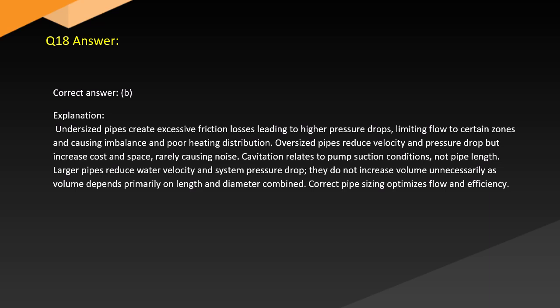Answer. Correct answer, B. Explanation. Undersized pipes create excessive friction losses leading to higher pressure drops, limiting flow to certain zones and causing imbalance and poor heating distribution. Oversized pipes reduce velocity and pressure drop but increase cost and space, rarely causing noise. Cavitation relates to pump suction conditions, not pipe length. Larger pipes reduce water velocity and system pressure drop, but they do not increase volume unnecessarily, as volume depends primarily on length and diameter combined. Correct pipe sizing optimizes flow and efficiency.